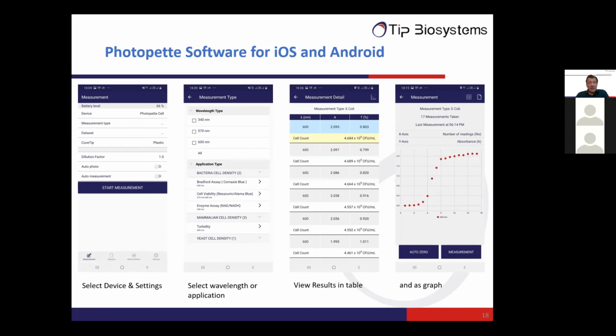The software will guide you and will ask you first to do an auto zero in your buffer or media, and then perform your sample measurements. Your sample measurements are displayed in this view. This is the table view where you see at which wavelengths you have measured, which absorbance and corresponding transmission. However, if you do continuous measurements, for example for the enzymatic kinetic application at 340 nanometer, you can also switch to the graphic view by clicking this small icon, and then your numbers will be seen in a graphical format. If you do kinetic measurements, this is very handy and very cool because you can see directly how your results will develop and form your kinetics.